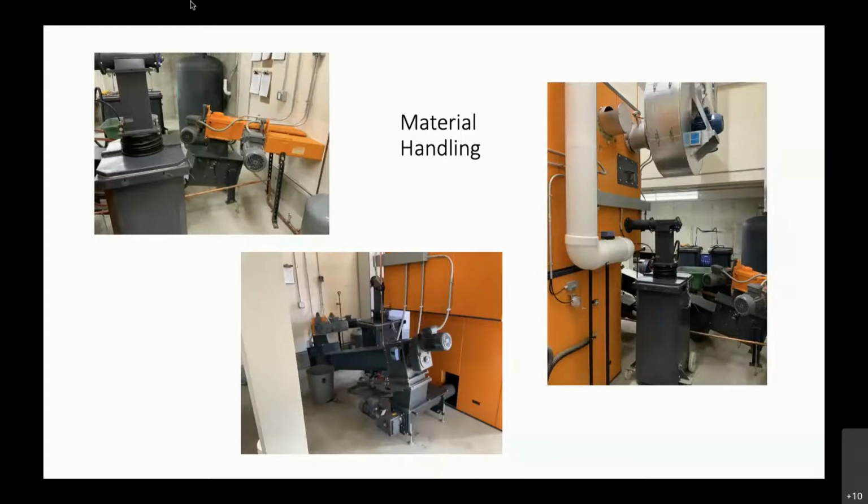The silo gets unloaded with a spinner. We call it the horizontal discharge unit, and there are several different designs of that spinner. We have found that this design is a very stout and reliable design because it has two motors. Sometimes the spinner and the augers are combined as a single unit, with a right angle gearbox from the auger that drives the spinner. But we like the two motor application here because, first of all, it's a little bit of redundancy. Also, if you have material that bridges more, you can increase, through the controller, the cycling time of that spinner. And so it gives you a little more option in terms of how you want to run that.